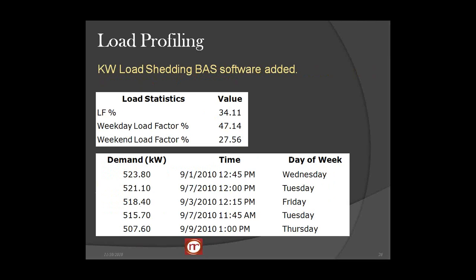Now, this year, we installed load shedding equipment. Now, you see our load factor is up to 47%. That's great during the week. Now, you see our kW is down to 523. What we did, and you notice that instead of just Mondays, it's different days of the week. You can see Wednesday, Tuesday, Friday, and so forth. But 523, well, we went down to 141 kW. That's over $1,000 a month savings by installing this. Well, the typical cost of this project may be $4 or $5 grand. And if I save $1,000 in a month, it doesn't take long to pay for it.